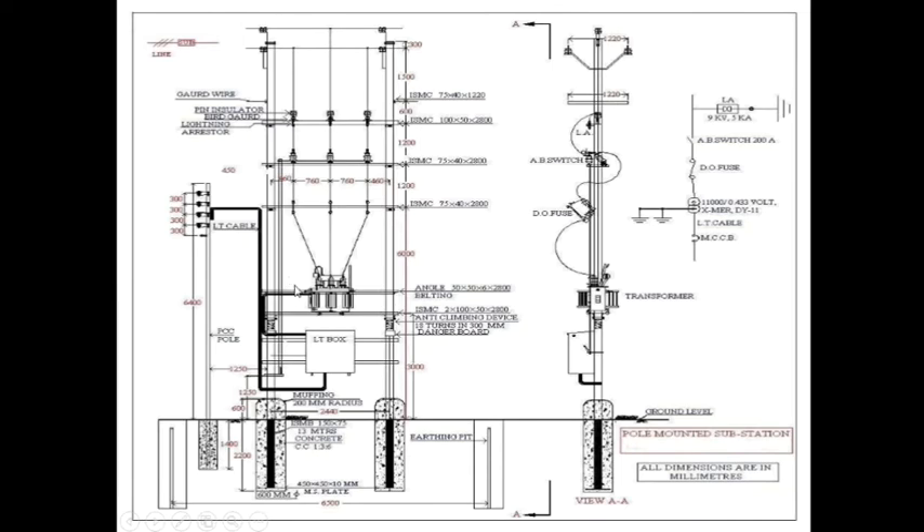This is a pole-mounted substation. Here, incoming 11 kV — this is the LA, which is earthed. The capacity of this LA is 9 kV, 5 kA. And this is the AB switch of 200 ampere. This is the D.O. fuse. This is a transformer of 11 kV by 433 volt. This is the LT cable. This is the moulded case circuit breaker, MCCB.